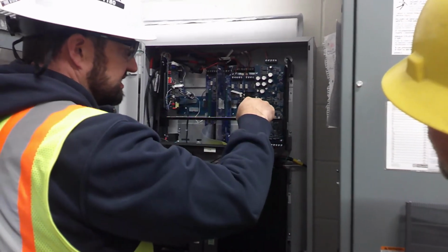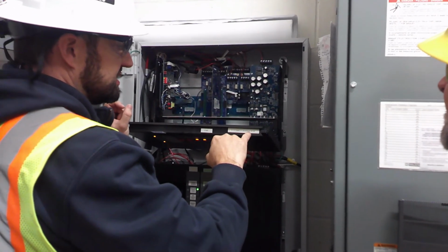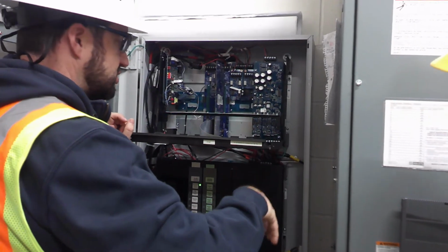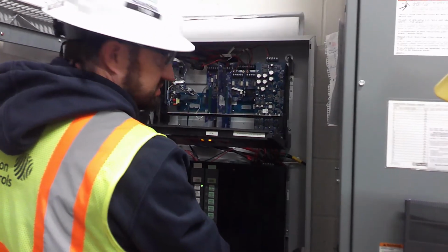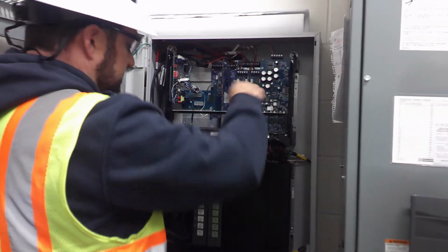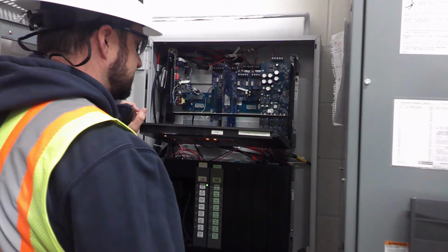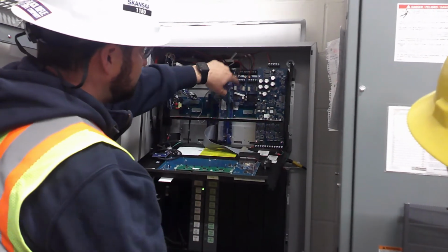You'd have to look at a set of prints to truly say. If you look at a set of prints, it will say A1, A2, and A3 to designate what strobe and what speaker circuit. So it would say A1-S1. So you would know that strobe is on A1, but also has speaker circuit 1 on it. So when you go to troubleshoot things like that, right up here, these are your IDNet cards.